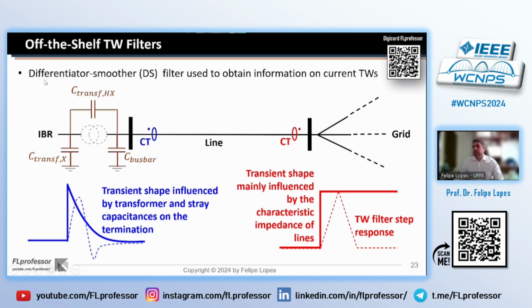Considering off-the-shelf devices, the traveling wave filter that has been used is the differentiator-smoother filter, which we call here the DS filter. Basically, this filter responds to a step change with triangular-shaped outputs. And when the step change starts to be attenuated, forming a ramp change, the filter starts to respond with a parabola-shaped output. So we expect to see shapes almost like triangles on the grid side, but since we are expecting this pattern here of transients, the output of the DS filter will tend to present a parabola, and then it will oscillate, and then it will converge.